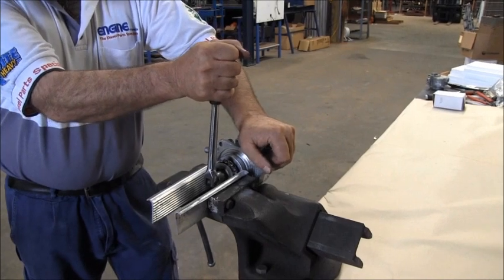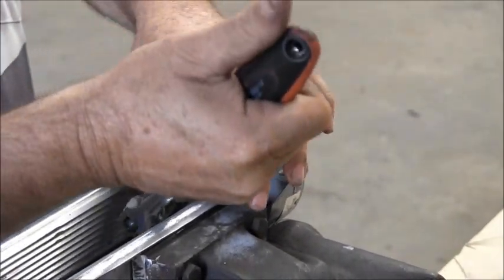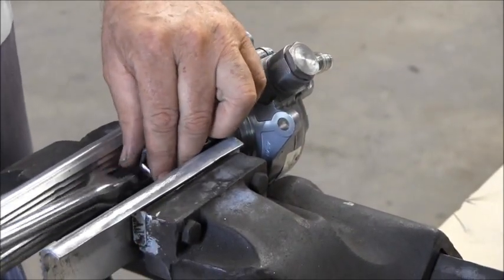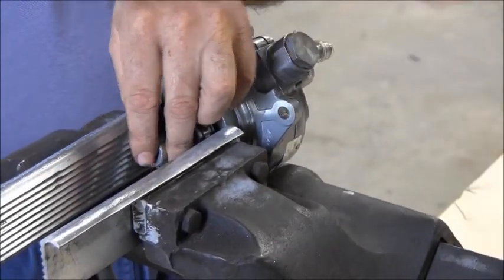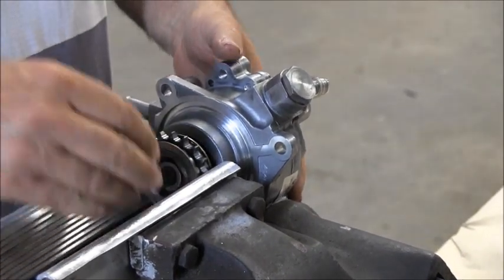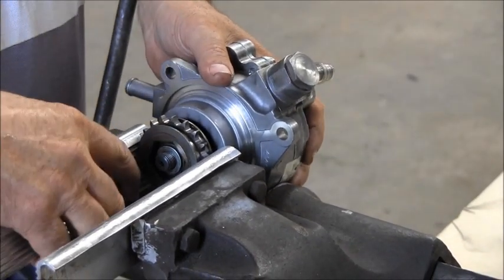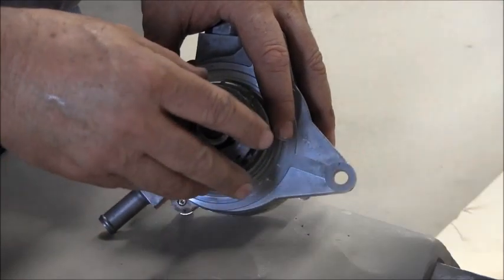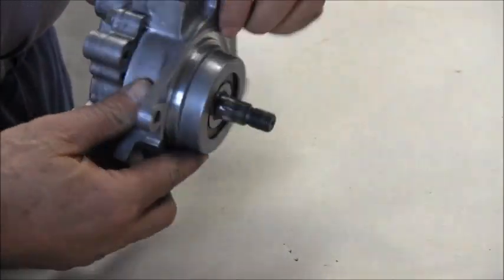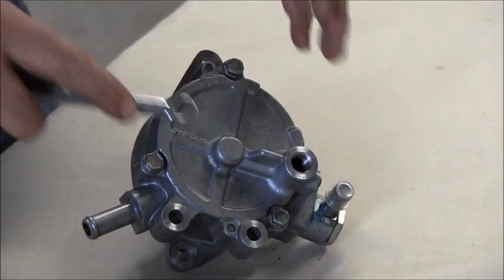To begin disassembly, grip the pump in a vise by the sprocket and loosen the main nut. Remove the washers and sprocket, then turn the unit over and undo the three bolts holding the housing and rear cover together.